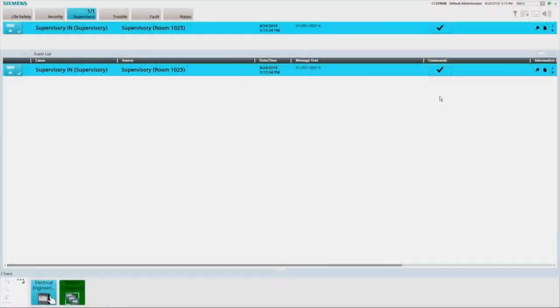A supervisory alarm is indicated in the summary bar by the blue flashing supervisory lamp and the blue flashing fire panel icon in the node map. In addition, a blue event will be displayed in the event list with a blue flashing event icon, and the workstation audio indicator will sound. To acknowledge the supervisory signal, press the acknowledge button in the commands column. The workstation audio indicator will be silenced and the supervisory lamp, event icon, and source fire panel icon will change from flashing to steady. When the supervisory condition has been cleared, you may need to reset the panel to restore normal standby by pressing the reset button.